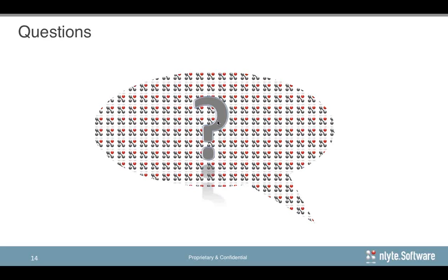Okay. Another question, will there be a specific Nlyte UI change as a result of the acquisition? It's kind of a big, juicy question. It is a very juicy one. There will be a new module in the front of the Nlyte system called Nlyte Alarms, which will give you the view where you can configure all of your alarms, and we'll be pulling the pages from FieldView into Nlyte. They'll be branded, all look the same, feel the same. You'll do all your stuff inside there for setting up your measurement points and tying those measurement points to the assets inside Nlyte. The visualization of an alarm and a threshold will all be on the floor plan, on the asset, in the logical row view. All that will be supported, and the email notifications will go out as well. So there will be a blended growth inside Nlyte, but there will be a whole brand new module.